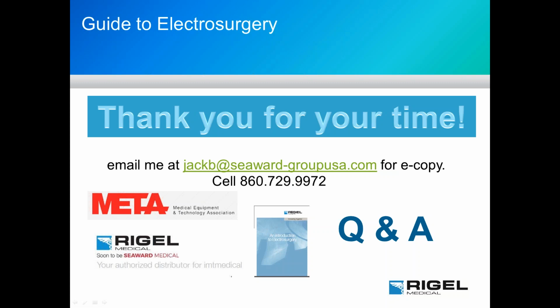Covidien, Valleylab, Medtronic products all do their pass-fail based on current. So they'll give you a range of current that they want the output to be within. A couple of other manufacturers are starting to do that as well. I've seen some CONMED specifications on their latest generator that way. So it all depends on the manufacturer and what they specify in the service manual, whether it is power-based or current-based.